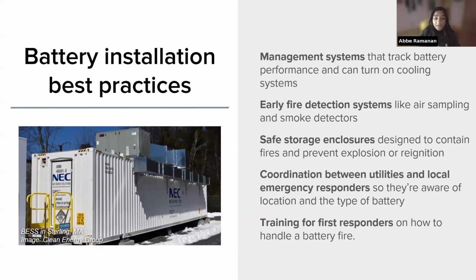With any battery storage installation, as long as it's installed following best practices, there's minimal safety risk. That includes having management systems in place to track performance, turning on installed cooling systems to prevent thermal runaway, early fire detection systems like smoke detectors and air samplers, and enclosing batteries in safe storage containers to minimize risk of fire spreading to other batteries. A big thing is making sure there's coordination between utilities and local first responders, so they're aware there's a battery storage installation and know the best practices for fighting a battery storage fire.